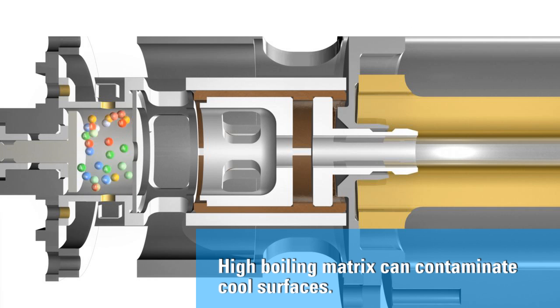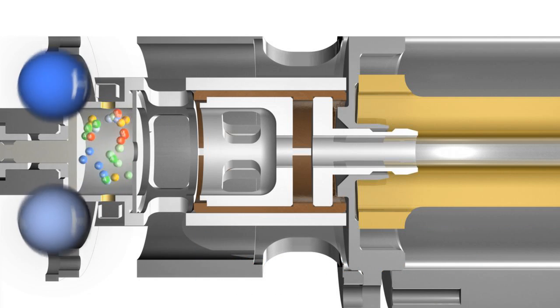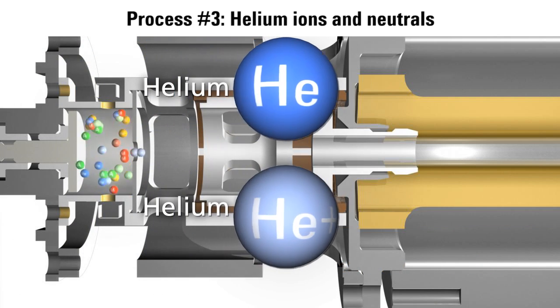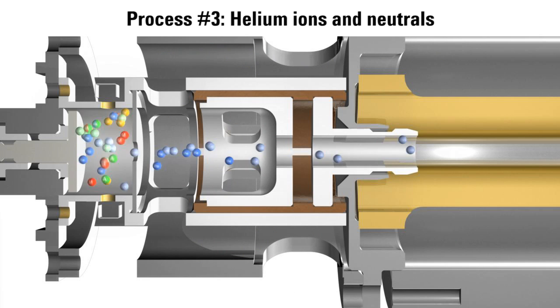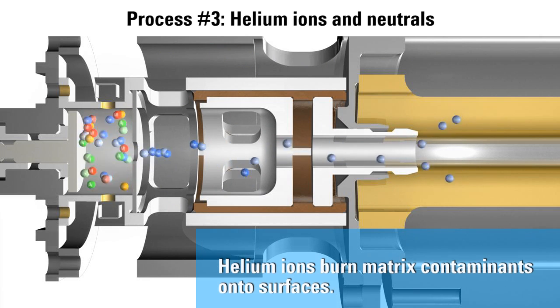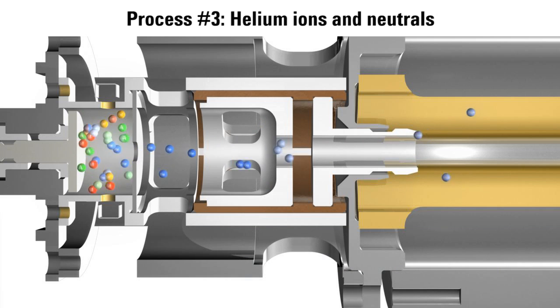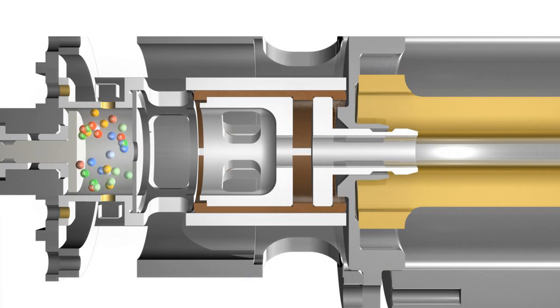As we think about the potential for contamination, we must not forget helium. The intense flux, high flow of helium ions helps to burn the high boiling molecules onto the surfaces of the source and the analyzer. The cooler the surfaces, the faster the rate of contamination, and the faster performance is lost.